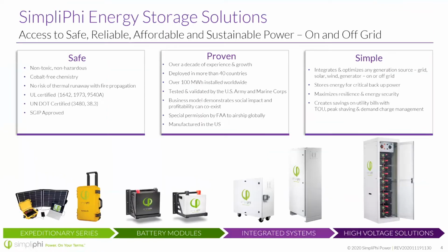Just a little bit on company history to start, for those that are not aware. SimpliPhi Power: safe, proven, simple technology. Safe is this non-toxic, non-hazardous, cobalt-free lithium chemistry, which takes away the risk of thermal runaway with fire propagation. UL certified 1642 on a cell level, 1973 on a battery level, and 9540, that should say 9540, not 9540A, I apologize for the typo, on a system level, as well as 9540A testing. UN DOT certifications 3480, 38.3, and SGIP approved for those in California.